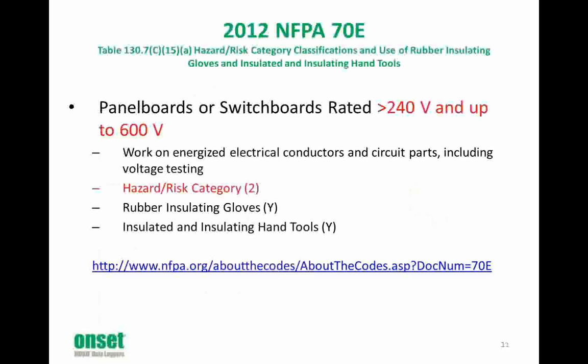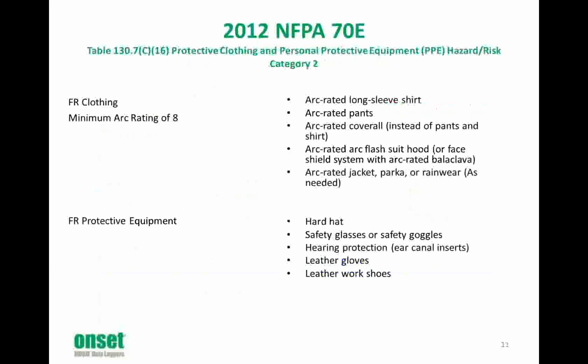And here's the latest safety standard that will follow. If we go over to Table 130.7 C15A in the 2012 edition of the NFPA 70E, Standards for Electrical Safety in the Workplace, this shows us that when working with panel boards greater than 240 volts and up to 600 volts, we must wear the safety equipment in compliance with Hazard Risk Category 2. Table 130.7 C16 shows the equipment associated with Hazard Risk Category 2. We will go over each piece in the following slides.